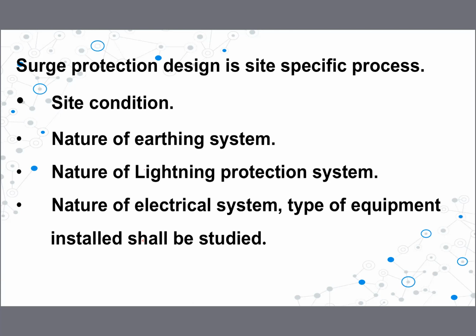It is also very much essential to study the lightning protection system in the building and how its conductors run inside the building, to understand the lightning protection zones. Then the electrical equipment, whether we need to protect it or not, has to be evaluated and studied properly. After studying all these conditions, we can decide at which place we need an SPD, what type of SPD, and what technical parameters of the SPDs we should use.